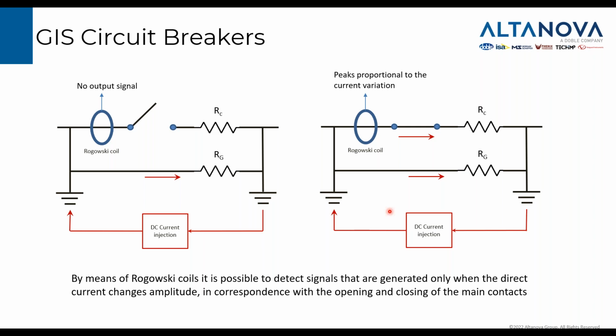So the solution is to introduce Rogowski coils in the path of the current in the main contact. So we have to keep the concept of the current generator. We need something that injects current, but we have to detect the moment where the current flows only in the contact. Because if you measure the total current out from the DC generator, you will not see any difference, because the current that flows into this, let's say, network is basically always the same. But the Rogowski coil gives us the possibility to detect when the current flows into this branch of the network.